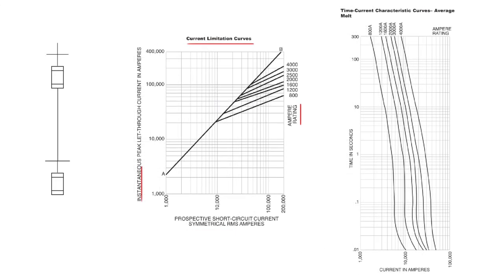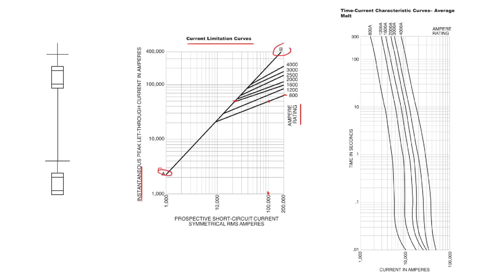Let's do an example of an 800 amp fuse. First we look at the amp rating of the fuse, which would be here, so we're interested in this line. Then we're going to say there's 100,000 fault current amps. We see where the fault current intersects the 800 amp line, which is right around here, and then we go over to where it intersects the AB line, somewhere around here. Then we drop straight down to right around here, so there's around 21 to 22 kiloamps of fault current let through.